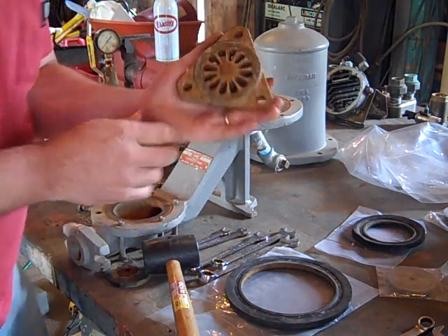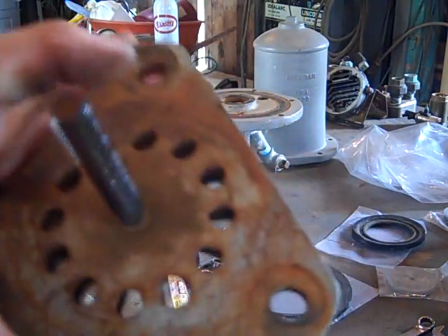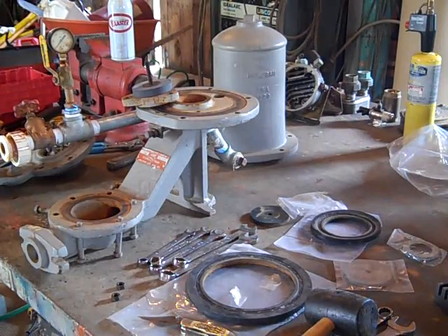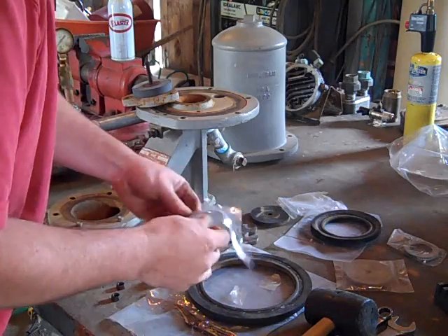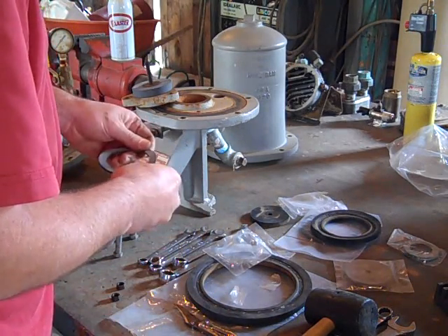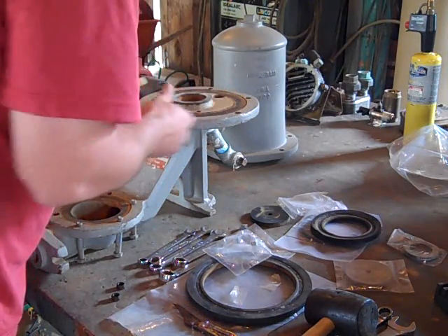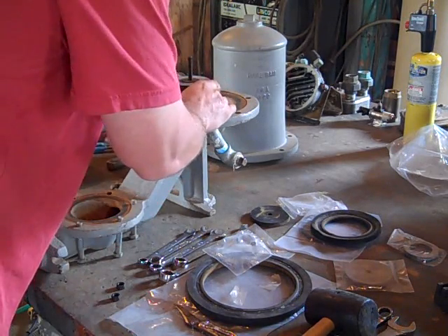It's in pretty good shape. See these old castings — they're pretty cool. The fish actually just got kind of extruded through there to the other side. Anyway, this gasket is okay. I've cleaned everything out. These nice new gaskets — my old gaskets are really not in bad shape, so I'm going to package them back up and keep them as a backup set, but I'm going to go ahead and put a new set of gaskets in this ram.